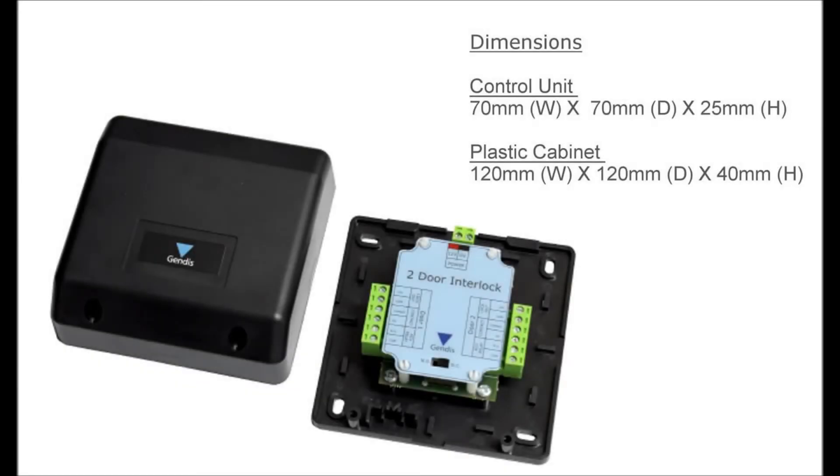This is the Gendis two-door interlock, sometimes called an airlock device. It's a small device powered by the controller or lock supply and has a simple switch towards the bottom of the wiring label that selects between normally open, as is typically a lock release, or normally closed, such as a maglock. Both doors must use the same lock type.